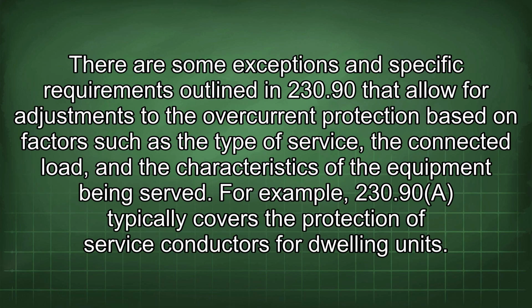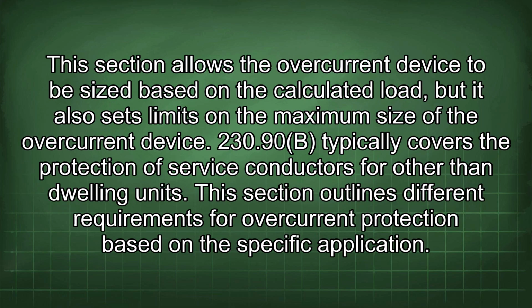There are some exceptions and specific requirements outlined in 230.90 that allow for adjustments to the overcurrent protection based on factors such as the type of service, the connected load, and the characteristics of the equipment being served. For example, 230.90(A) typically covers the protection of service conductors for dwelling units. This section allows the overcurrent device to be sized based on the calculated load, but it also sets limits on the maximum size of the overcurrent device. 230.90b typically covers the protection of service conductors for other than dwelling units. This section outlines different requirements for overcurrent protection based on the specific application.